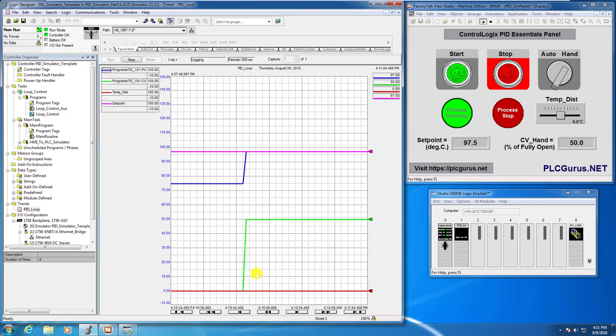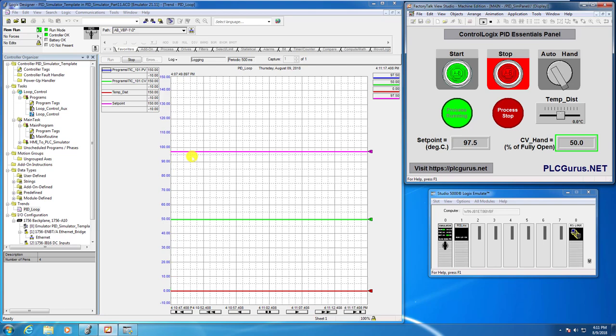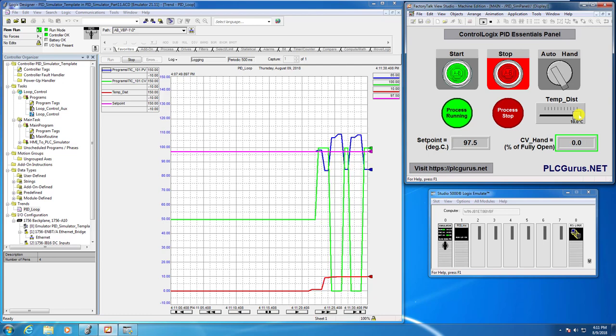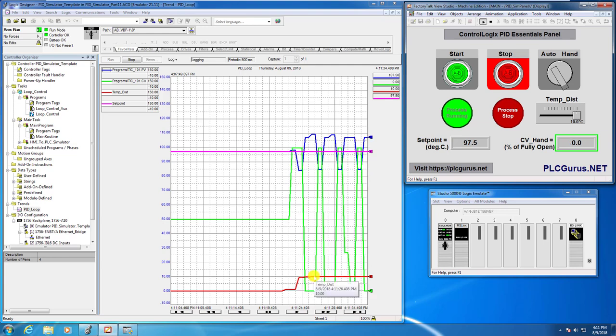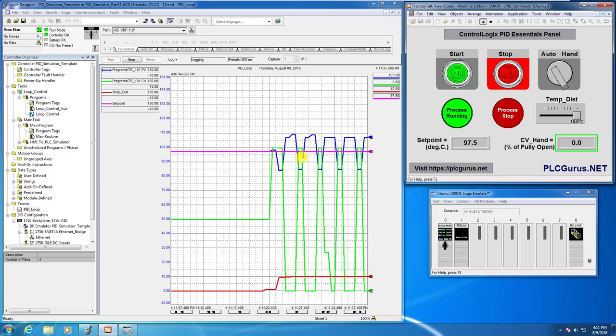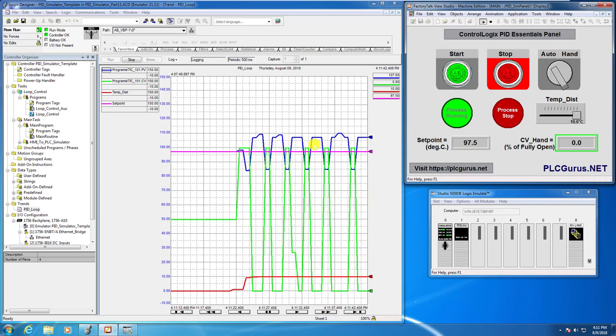Let's head back to our trend — there we go, we see that immediate response. I'm going to kick it into automatic mode. We're in auto now and we have stability; nothing is changing, we're at exactly set point with zero error. But watch what happens when I introduce a disturbance — I'll slide that up and inject some heat into the process. You can see the temperature disturbance trend line increased to 10 degrees C, and now we run into that instability and uncontrollable oscillation.